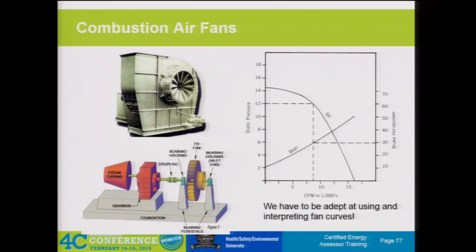When you get into some of the larger, more complex boilers, fans become an area where you could focus a lot of attention on energy assessment. On some of the solid fuel boilers, there are different levels of fans where you've got different air staging—putting tertiary air or secondary air into the system so you have directed air coming at different parts of the firebox to help complete combustion and minimize carryover of particulates. Things you can see with fans include: dampers with damaged actuators where the operator is trying to adjust but the linkages aren't working. During tuning, if you're trying to adjust the air and the emissions profile's not changing, then something is going on with the damper or the fan system. Nowadays, depending on the application, fans may have a VFD or some other drive to be more efficient and control the fan speed as well.